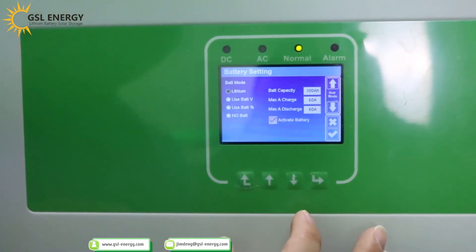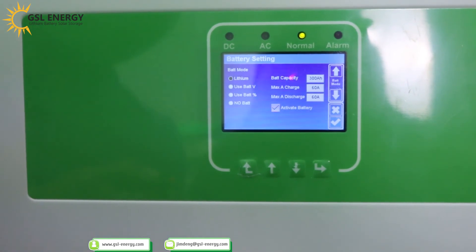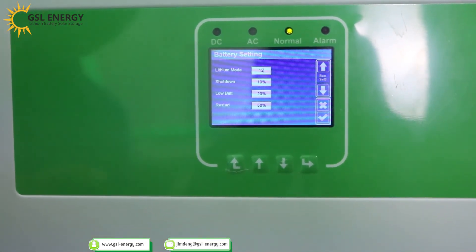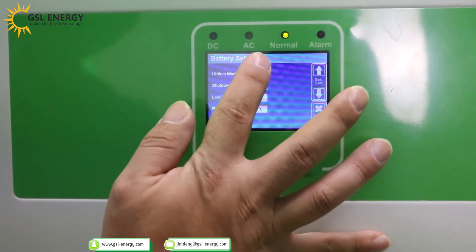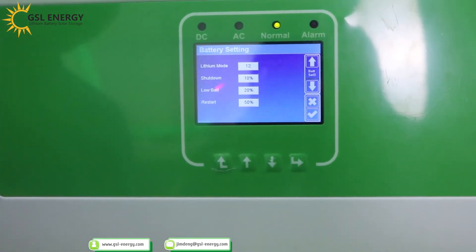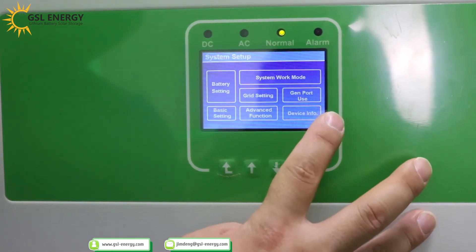Check the battery setting: battery type is Lithium battery. Battery capacity: 300Ah. Max charge and max discharge settings are shown. Grid charge option is available. In battery settings, select Lithium battery. Set shutdown at 10%, low battery warning at 20%, and restart at 50%. After finishing the changes, press the right button to confirm the settings.